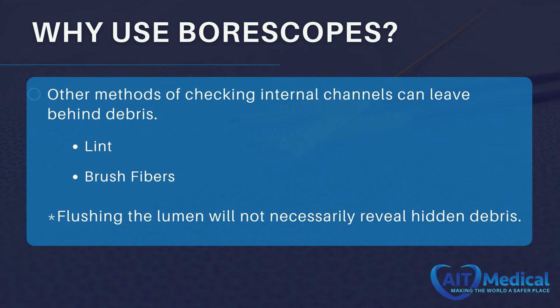Borescopes aren't the only solution for checking the cleanliness of lumens and cannulas. Many facilities use cotton pipe cleaners or nylon lumen brushes. The challenge with both is that they can leave debris behind in the lumen. Even the best quality low-linting pipe cleaners will leave behind some amount of fuzz or lint. Nylon bristle brushes are also problematic — brush fibers can detach and stay in the cannula. Additionally, having cleaning brushes on the clean assembly side of the department encourages technicians to perform device cleaning, which should only be done in the decontamination area.